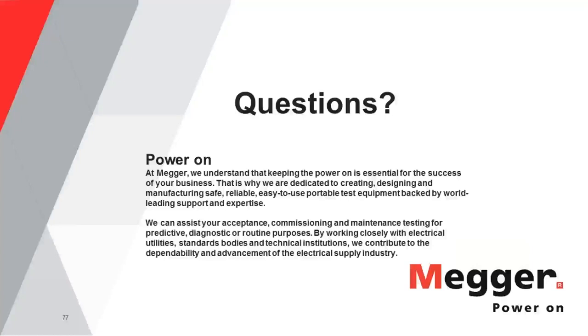The DAR is like a PI, but with shorter time intervals, 30 seconds into 1 minute or 1 minute into 3 minutes. Those are the new values that are typically being used in DAR testing, because the absorption times are becoming much shorter on these newer insulating materials, and basically that's what accounts for the DAR test. And so especially if you know you're working on old equipment that's been around for quite a while, maybe you can stick with a PI. But if you're on newer insulating materials and real high-end stuff, go to the DAR test.